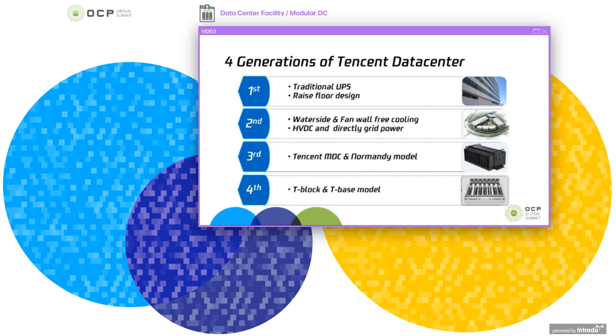Second generation is our self-built facility in Tianjin as a reference. We introduced water side and fan wall free cooling, plus a new power model with hybrid high voltage DC and AC. AC is direct grid power to the system, and we achieve PUE of 1.4.